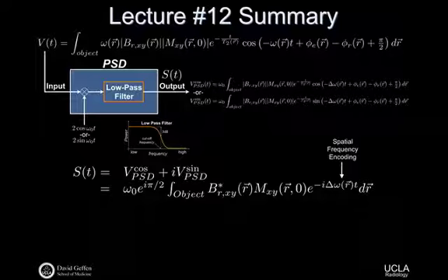And so the time-based signal that we receive after the phase-sensitive detection, after doing the quadrature detection and adding the signals together, just depends on the receiver sensitivity, how good is your coil, what's the state of your transverse magnetization, and in fact, how did you spatially encode it? I'll give you some pictorial examples of what this really means. But this allows us to sample magnetization for specific spatial frequencies. And that will get us closer to an understanding of how MR does spatial localization and image formation.